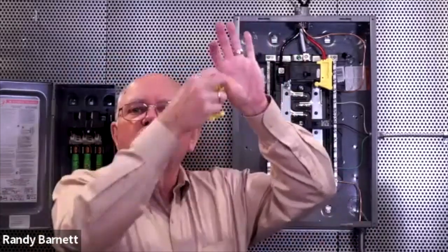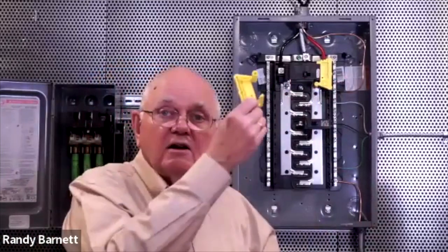And that's where we come off of a larger conductor with a smaller conductor, unprotected. We tap onto these larger conductors and we take smaller conductors, and they don't have any protection until they get to that first disconnect inside of a panel. Well, once again, we would have unprotected conductors coming into our panel. So in that case as well, we're going to have to put the barriers in place. So let's look at some of these requirements in the code and see just what we're talking about.